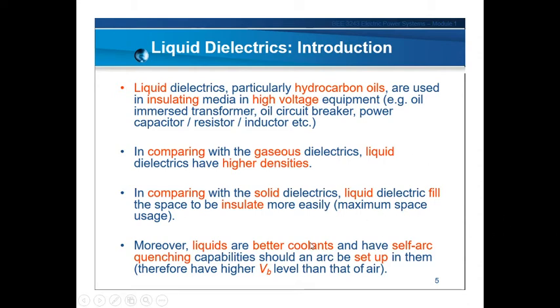Moreover, liquids are better coolants and have self-arc quenching capabilities, should an arc be set up in them. In terms of liquid, they do not actually serve only as insulators; they have cooling properties, especially when used in high voltage equipment. So the liquid in a transformer oil serves two purposes: one as a coolant, and another for providing insulation.